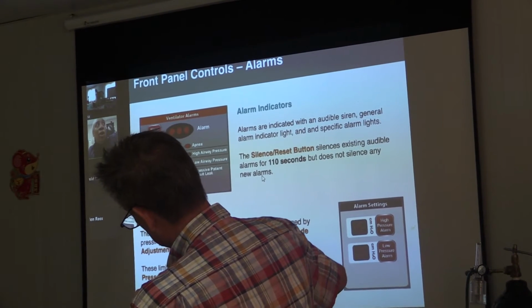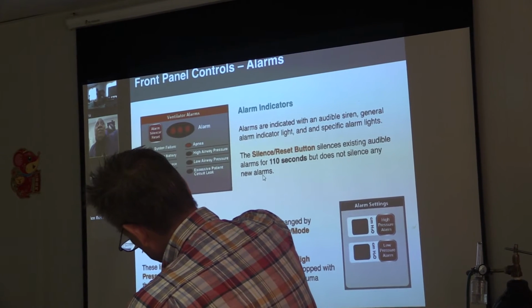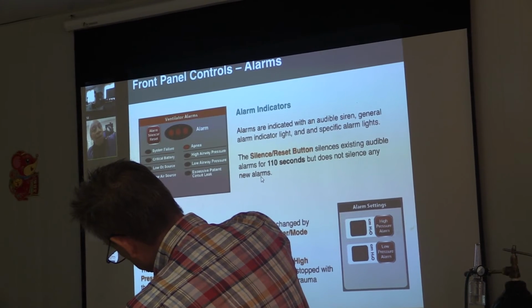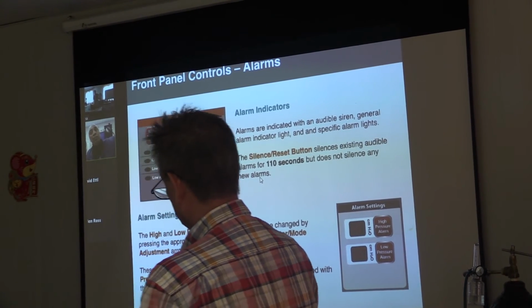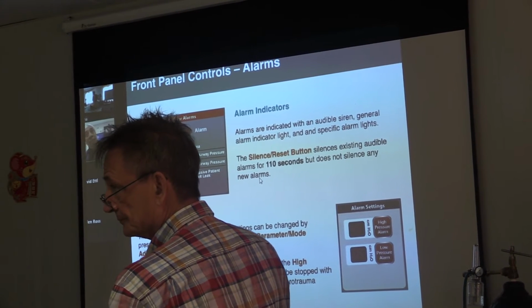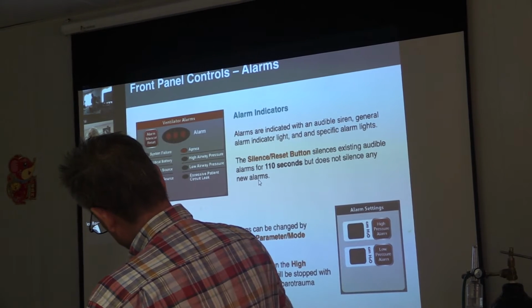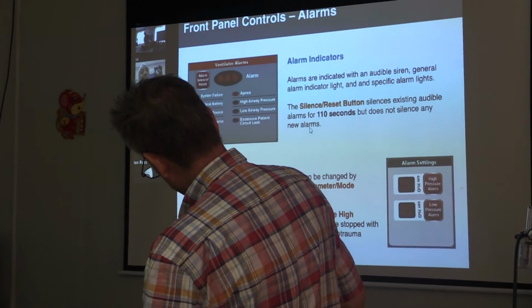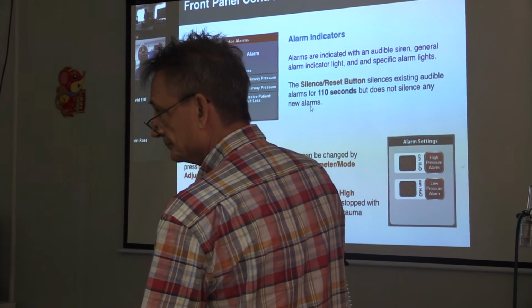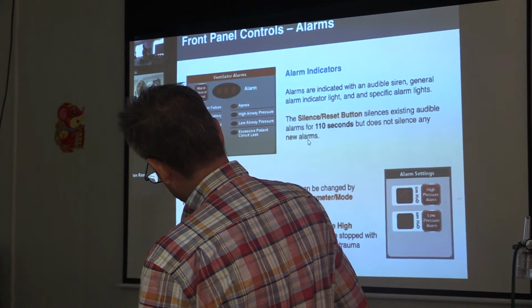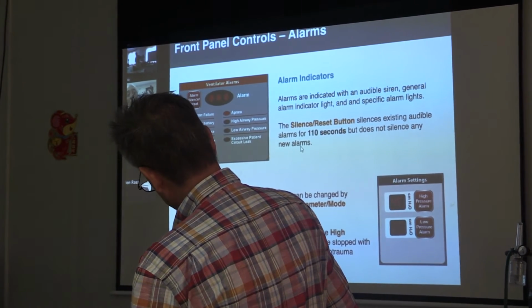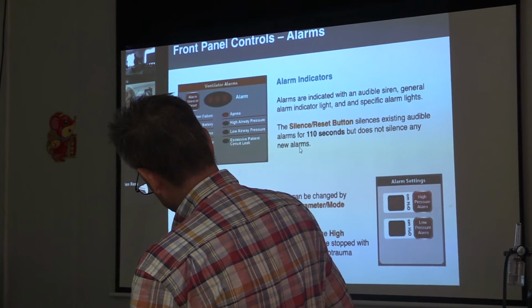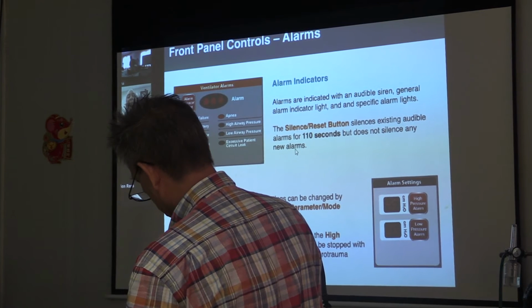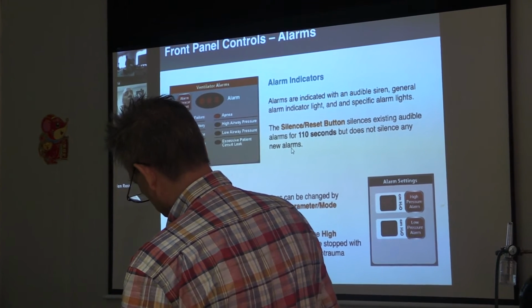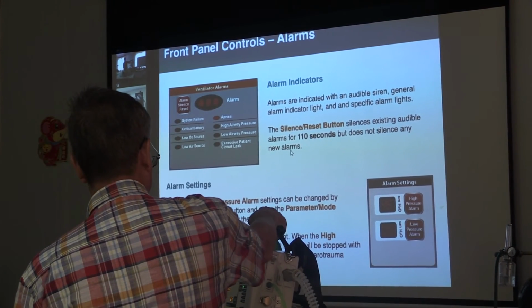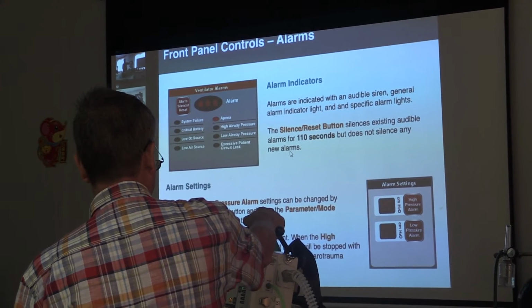The low pressure alarm is very important, because if it is ringing, you should look and see whether the ventilator is actually giving the right tidal volume. You may find that the ventilator is not really giving much of a tidal volume because maybe the patient has become disconnected, or there's a leak in the tube, or the cuff of the endotracheal tube has a hole in it and is leaking. You can feel the leak by putting your hand over the patient's mouth perhaps. So the low pressure alarm is often telling you that there's a problem in your circuit somewhere.